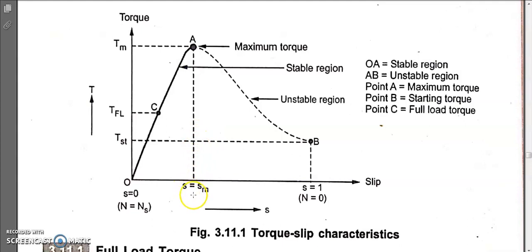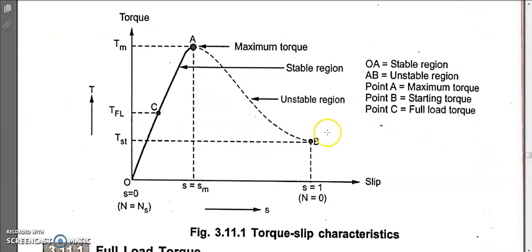Point A is where maximum torque occurs. At maximum torque, the maximum slip s equals sm equals r2 divided by x2, where r2 equals x2. Note that the maximum slip value cannot exceed one. Point B is the starting torque point, where motor speed is zero — that's why it is called starting torque.